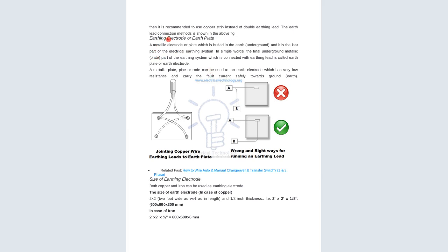Another thing that we have is the earthing electrode, or earth plates. The metal electrode or plate which is buried in the earth, that is underground, is the last part of the electrical earthing system. In simple words, the final underground metal plate that is part of the earthing system and is connected with the earthing lead is called the earth plate or the earth electrode. The metallic plate, pipe or rod can be used as an earth electrode, which has very low resistance and carries the fault current safely towards the ground, that is towards the earth.